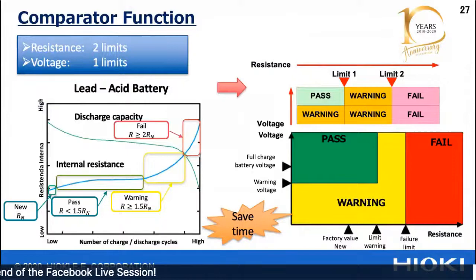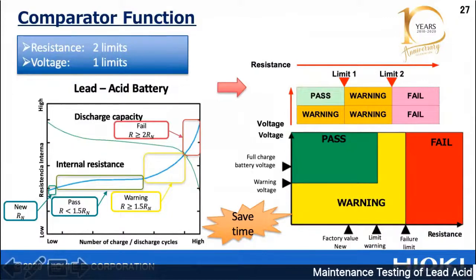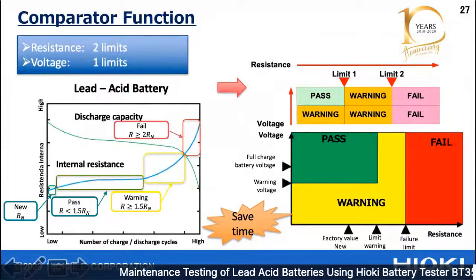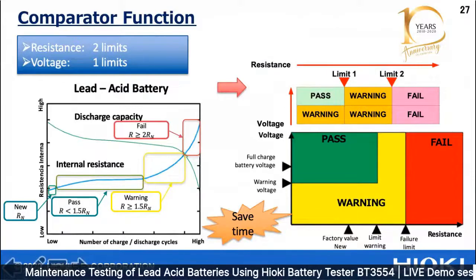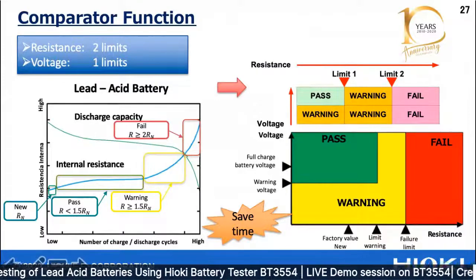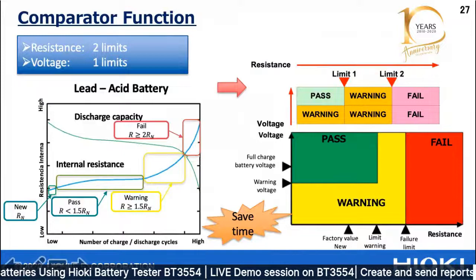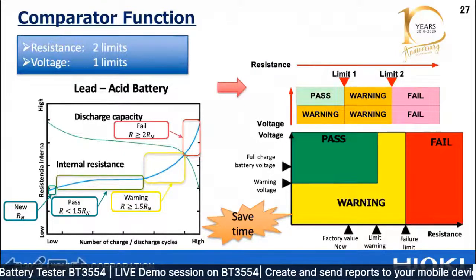We have three states: pass, warning, and fail. Pass means the battery is good. Warning means you need to do maintenance and monitor the battery more often. Fail means the battery is not good and must be replaced.